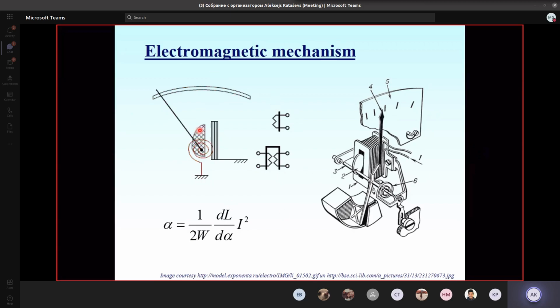Another feature of the electromagnetic mechanism is that it usually needs a damper. Here is an example of how the damper looks: it's a curved box with a flag moving back and forth. The role of the damper is to provide viscous friction to stop the oscillation of the index after the device is switched on.